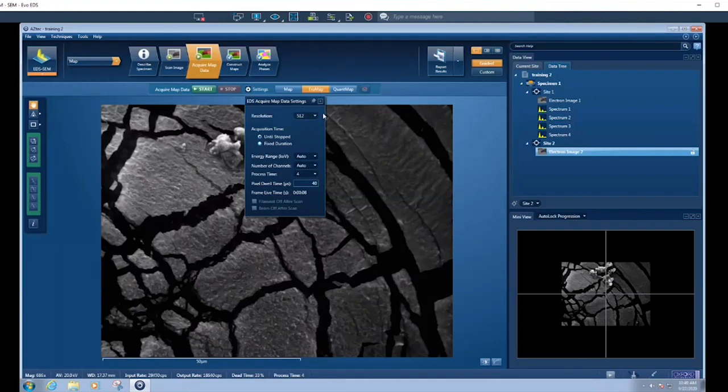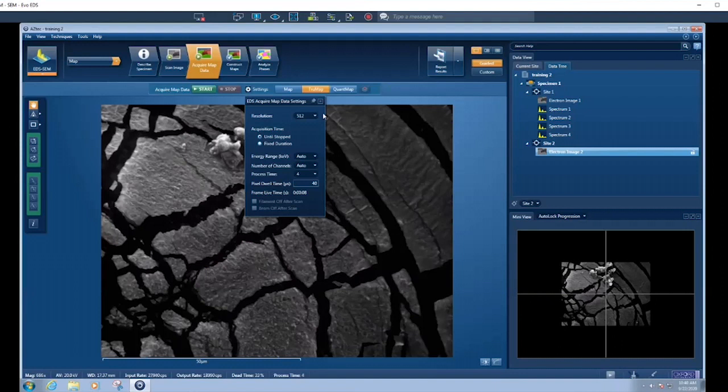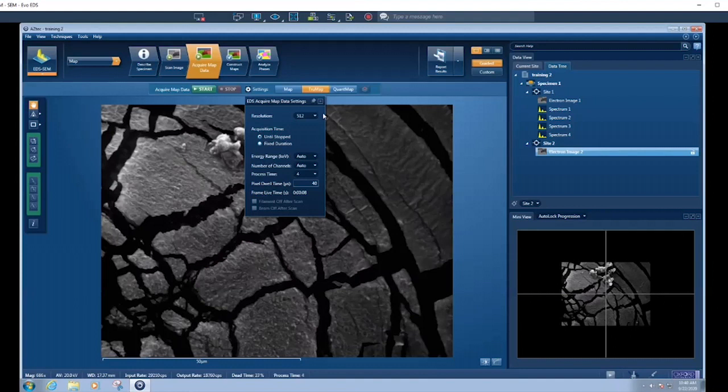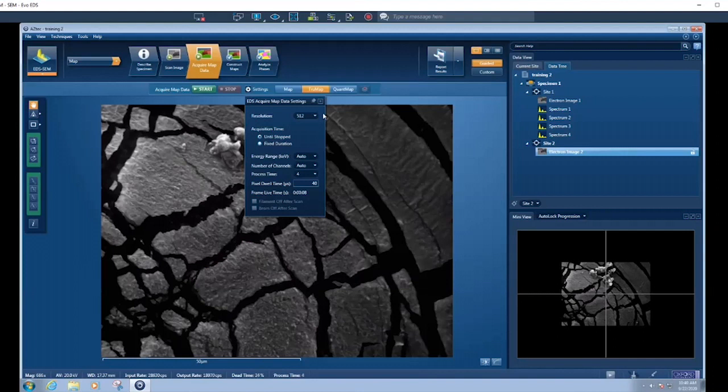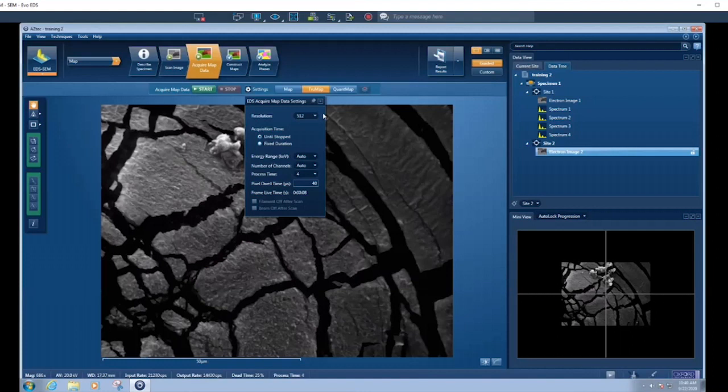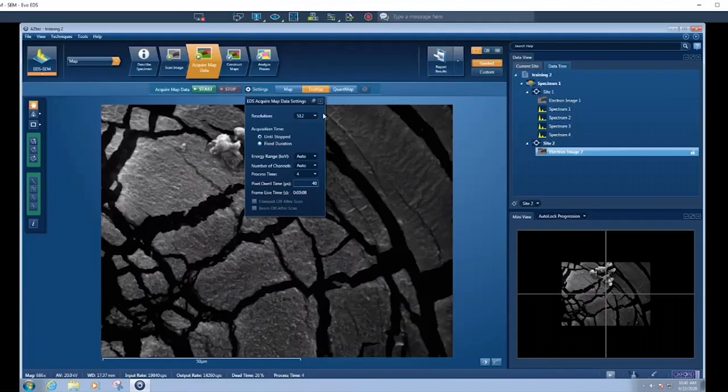Yutaka's asked, why does the sample drift if it's in a secure place? The sample itself is not moving, but with field charging, thermal and magnetic field drift issues can occur. If something external to the microscope changes, someone turns on a light switch or a piece of equipment and the local magnetic field changes, then the beam will be pushed slightly. We're only talking a few microns or a micron or less. Inside the microscope or inside the sample, as we're putting the beam down, the local field effects and local charging will also change where the beam is positioned, which will cause the beam to move slightly.